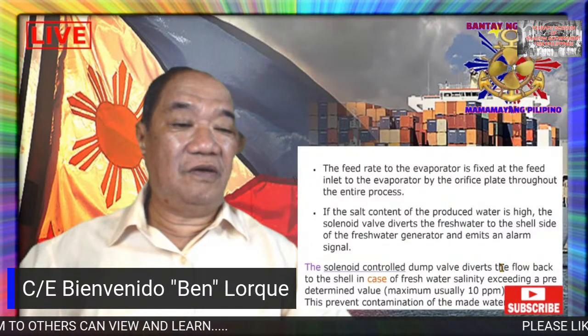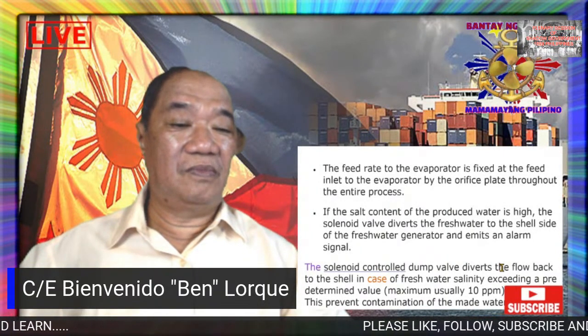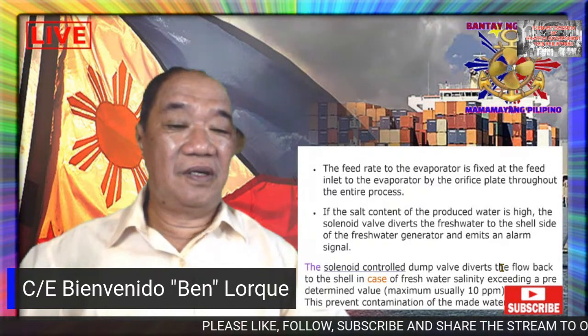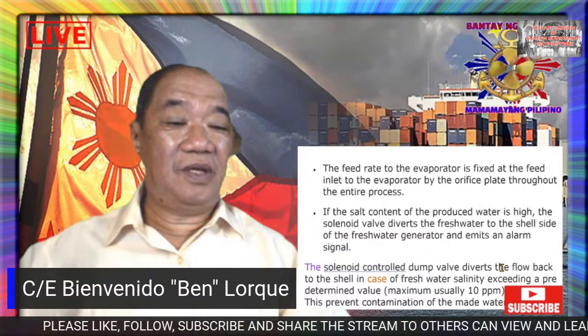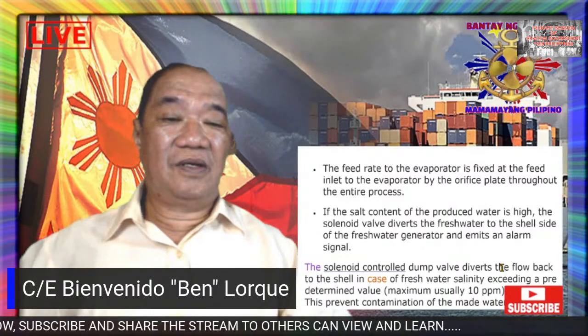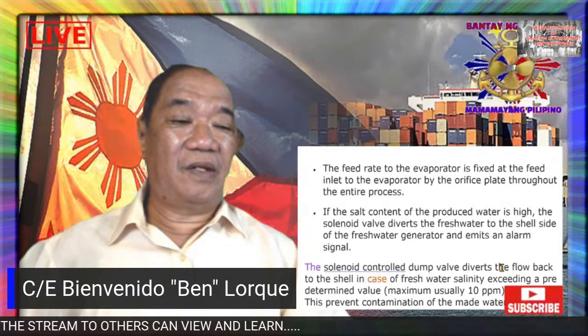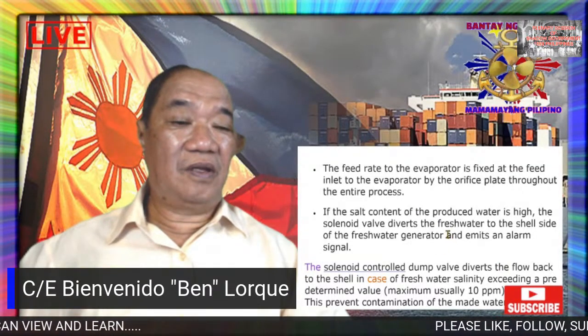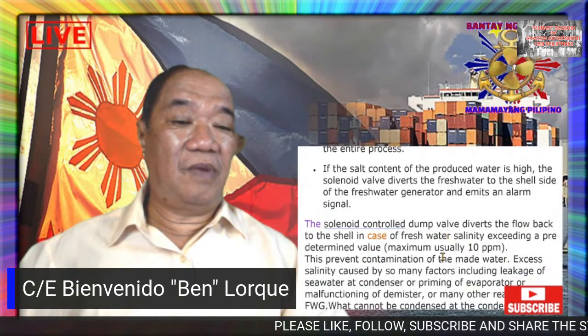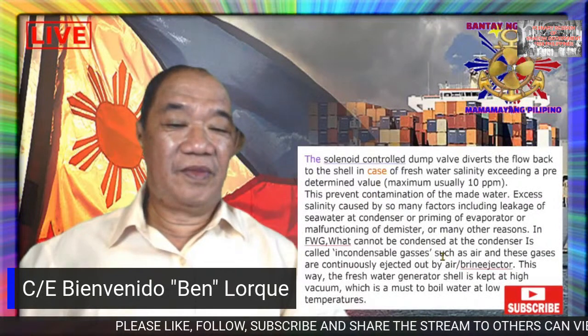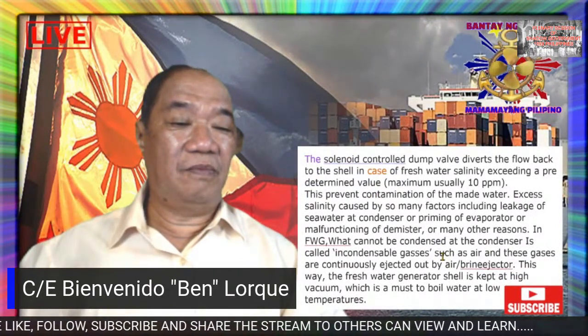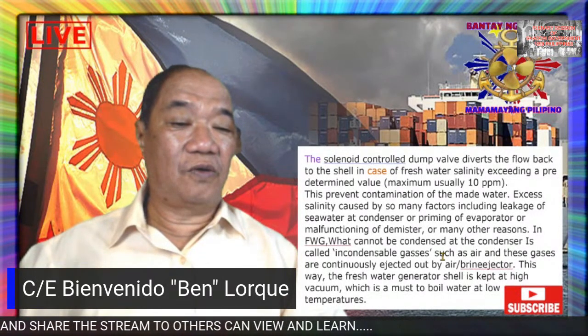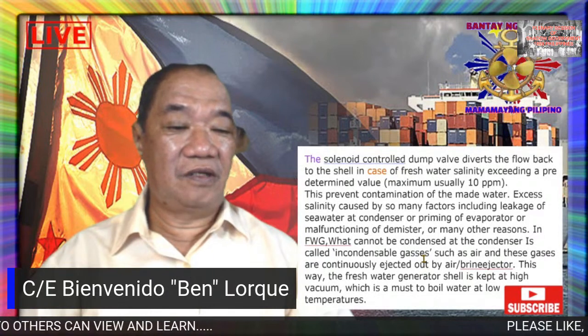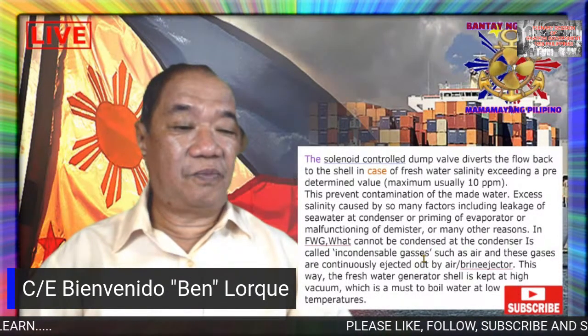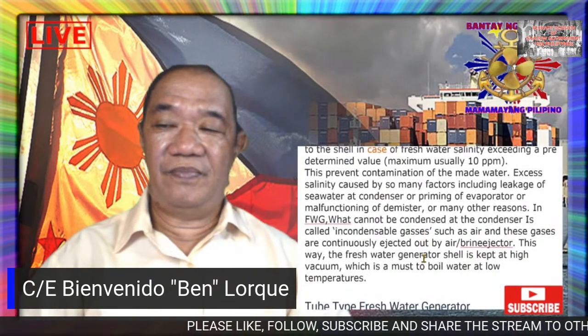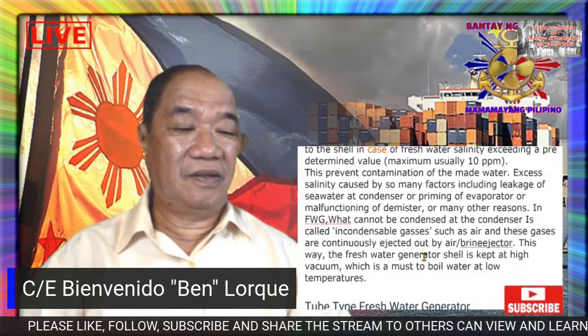So if the salt content of the produced water is high, the solenoid valve diverts the fresh water to the shell side of the freshwater generator and emits an alarm signal. So the solenoid-controlled dump valve diverts the flow back to the shell in case the freshwater salinity exceeds the predetermined value, maximum usually 10 ppm. This prevents contamination of the made water. Excess salinity is caused by many factors, including leakage of seawater at the condenser, priming of the evaporator, malfunctioning of the demister, or many other reasons.